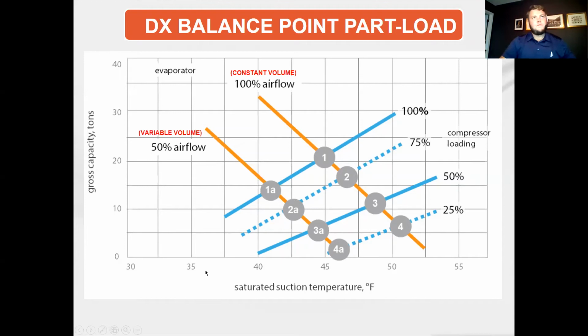Actually, it's the frosting of the coil. If we get too close to 30 degrees, the refrigerant that is in the coil would make ice on the fins, and eventually you can actually freeze up the coil to where air won't flow through it anymore. So in HVAC, we typically try to avoid needing to have defrost on evaporators. It's heat pumps you can't avoid, that sort of thing, but with typical HVAC systems.